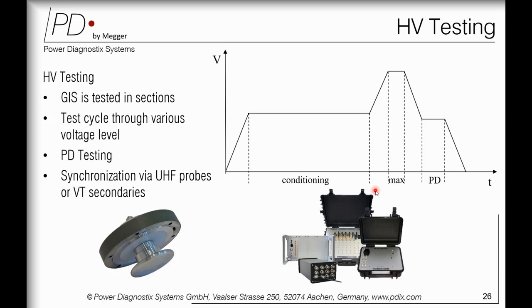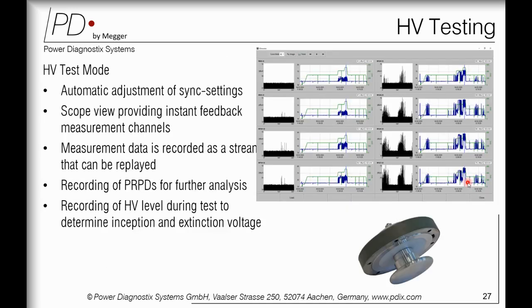So typically, during commissioning of the GIS, the end consumer and the OEM always ask to conduct HV testing. Once you have the GIS tested in sections, you have a test cycle at various voltage levels. That means you have rated voltage, then a higher level, 120%, to see the inception and extinction voltage of PD. Then again rated, and then you reduce the voltages. So there should be a dedicated HV test mode option in the software of your PD instrument. This is one image of your voltage versus current graph, including inception and extinction voltages.